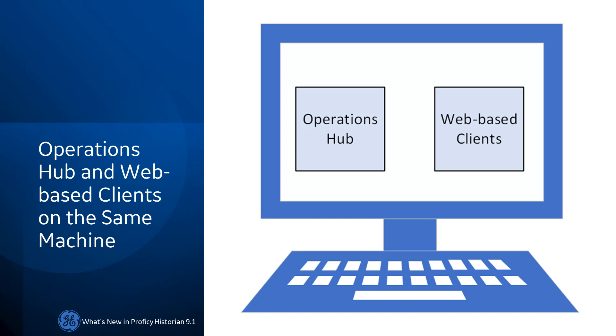Operations Hub and Web-based Clients on the same machine. You can now install Operations Hub and Historian Web-based Clients on the same machine. No additional configuration is required. The FQDN and the public HTTPS port of the application that you install first are used for the other one as well — you don't need to provide them again.